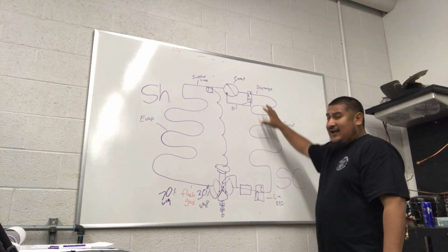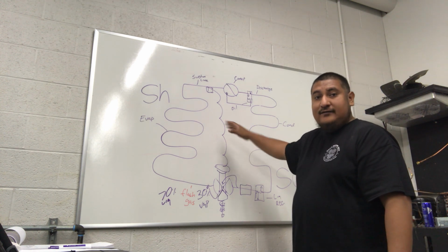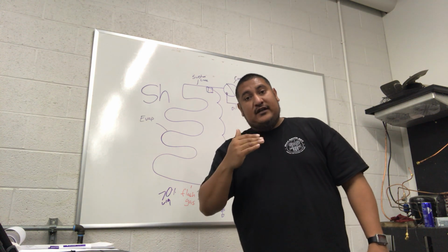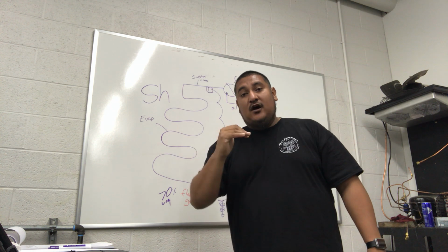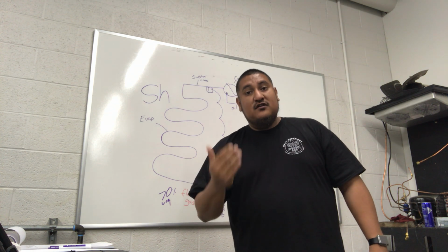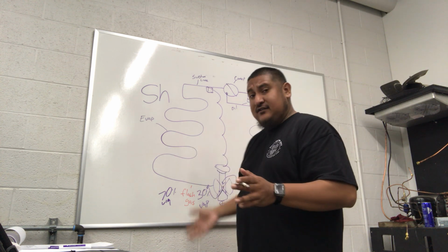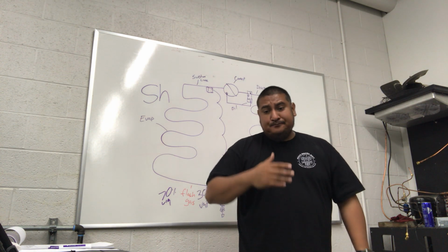Over here on our high side, that's what we're going to measure and see subcooling, all right? So again, if you guys remember, we're dropping it a couple of degrees, or 1 degree, or 10 degrees, 15 degrees, whatever degrees below its saturation temperature. That will give us subcooling, right? So again, just like I said, I'll draw something else here a little bit later on, or maybe in the next class.